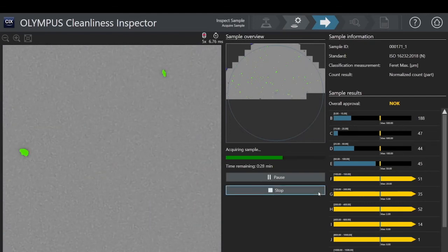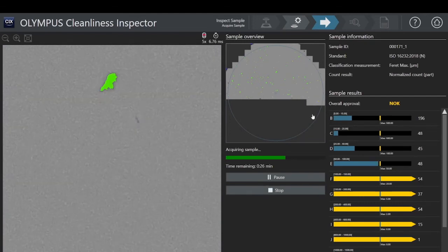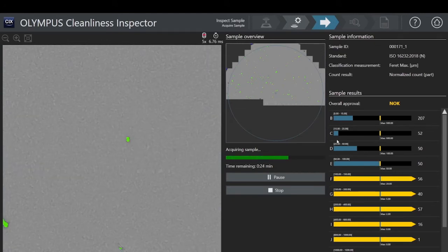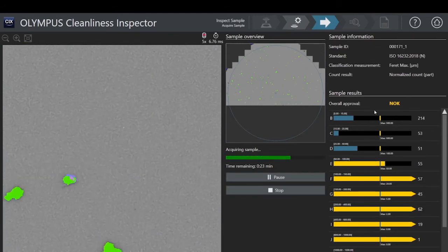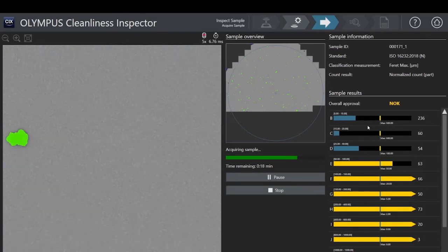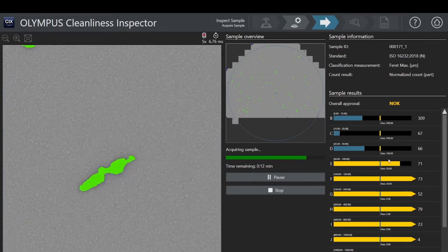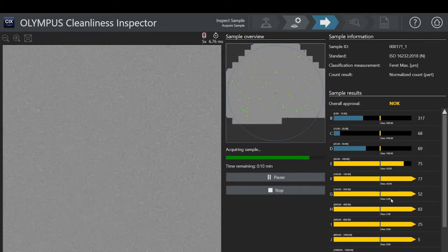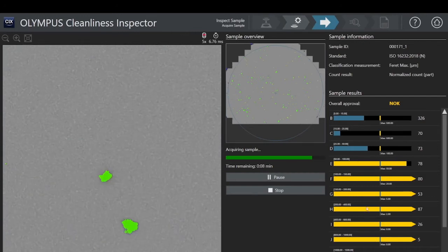As this is a collection of particles that I made from anything I had lying around, it's mostly large particles. It's remarkably hard to make these tiny 5 to 15 micron particles here, and if anyone has any advice, I'd appreciate it. But you can see our thresholds here at the 500, 500, 100, 50, 25, etc. And so we've well and truly failed up here.